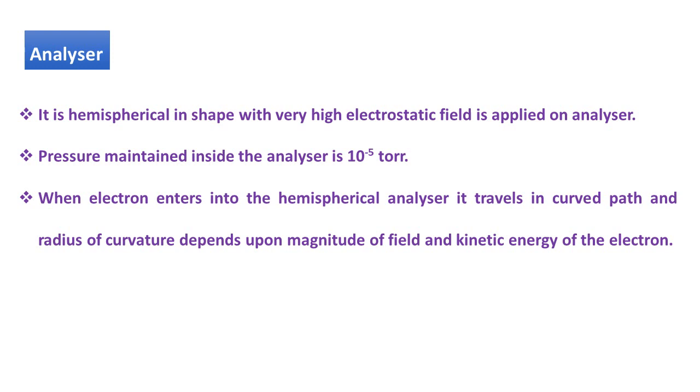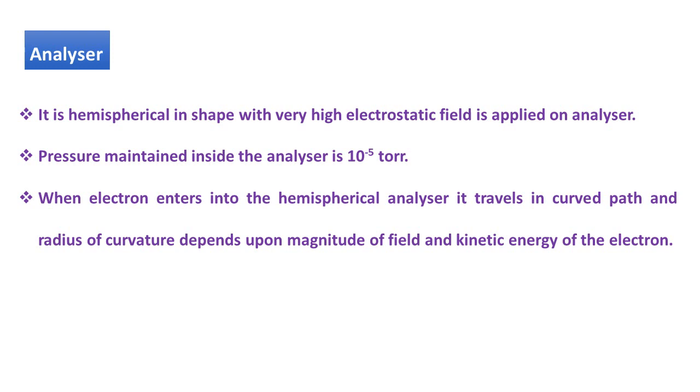Third is analyzer. Analyzer is hemispherical in shape with very high electric field applied on the analyzer. The pressure inside the analyzer is 10 to the minus 5 torr. When electron enters into the hemispherical analyzer, it travels in curved path and radius of curvature depends upon the magnitude of field and kinetic energy of electron.